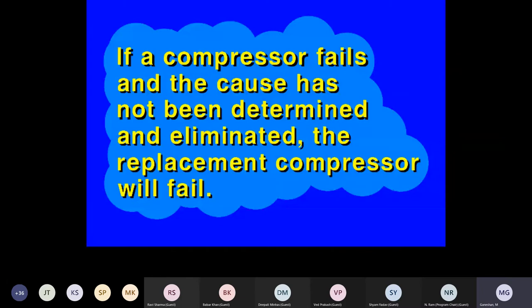Okay. If the compressor fails and the cause has not been determined, all the time they eliminate the failed compressors and replace them, and it will certainly fail again. There is no doubt about it. This is where we need to really take care of all these 7 things before we replace anything.